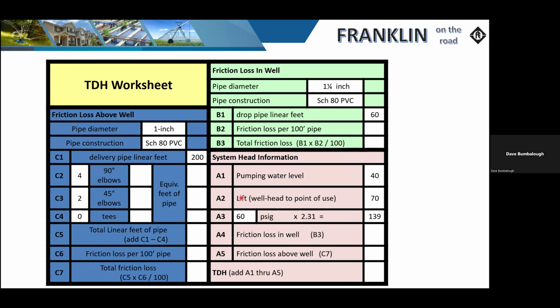So let's just say above the well, we've installed 1-inch pipe. Okay, it's a distance of about 200 feet. We've got about 4 90s and 2 45s, no T's. We'll go back to the chart and see what that equivalent is, and we'll add all this up. Now, as we go in the well, we've got it hanging on 1.25 inch, Schedule 80 pipe. It's roughly about 60 foot down from the surface down to the pump.